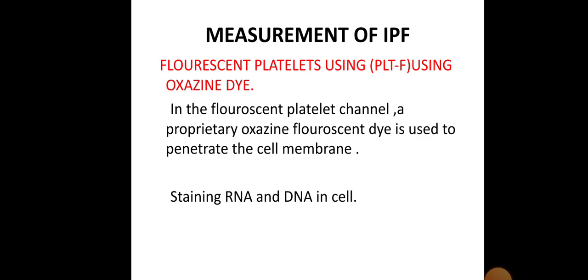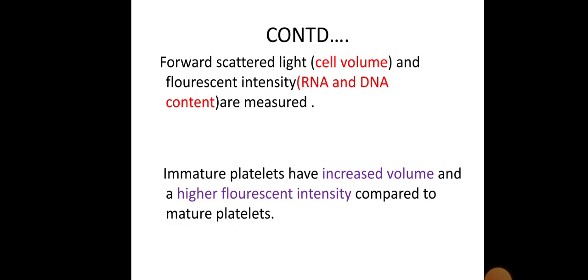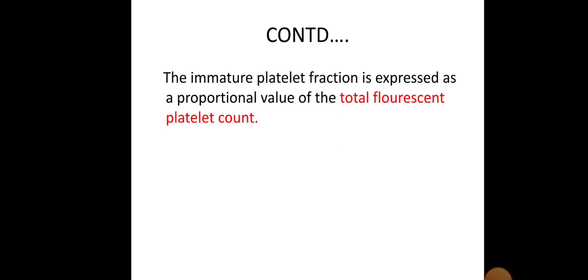Coming to how we measure the immature platelet fraction: IPF can be measured by fluorescence using an oxazine dye in the fluorescent platelet channel. A proprietary oxazine fluorescent dye is used to penetrate the cell membrane and stain the DNA of the cell. We measure forward scatter light and fluorescence intensity, where forward scatter light measures cell volume and fluorescence intensity measures the RNA and DNA content of the cell. Immature platelets have an increased volume and higher fluorescence intensity compared to mature platelets. The immature platelet fraction is expressed as a proportional value of the total platelet count.